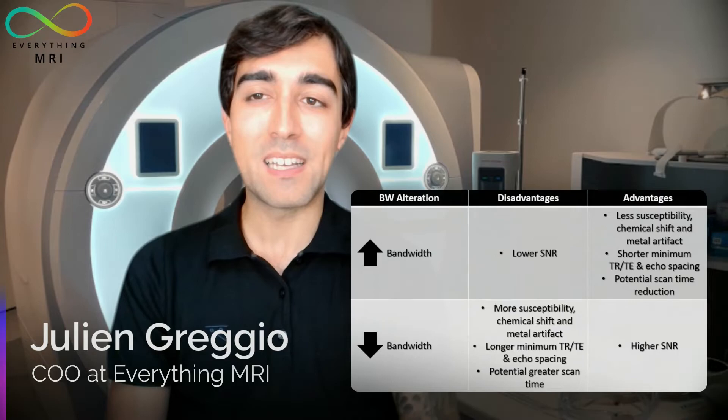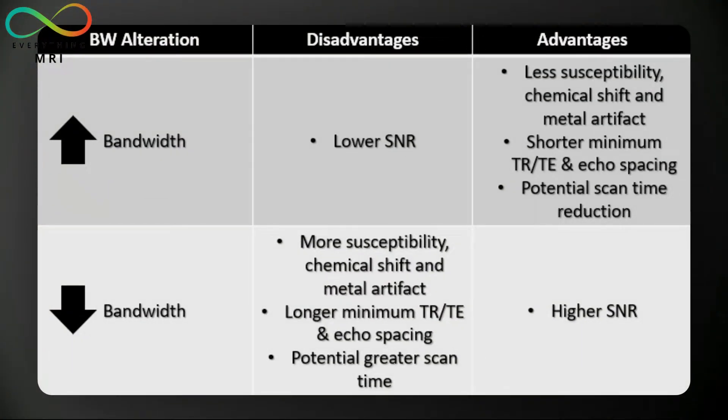A legitimate question is: do we ever decrease the bandwidth instead? There are a number of situations where lowering the bandwidth might be recommended, and this actually comes with several advantages on image quality. The main benefit of going down with the bandwidth is an increase in the overall SNR — and we're talking about a substantial increment. Halving the bandwidth, in fact, can increase the SNR between 30 and 40 percent.